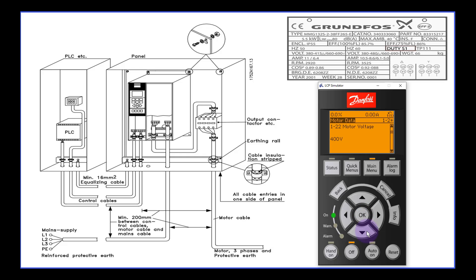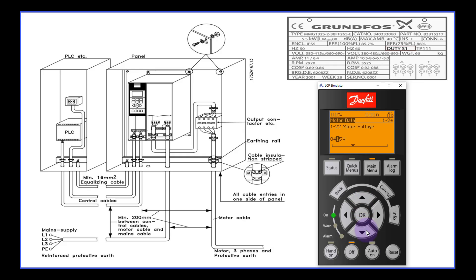Press the down arrow key to go to the next menu — motor voltage. Because my country's incoming power supply uses 50 Hz, I refer to the 50 Hz column. It depends on your incoming three-phase AC voltage. In my country, our three-phase incoming voltage is 415V, so I press the OK button and change it to 415V using the left or right arrow key, then press OK.